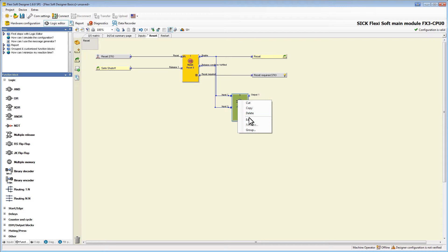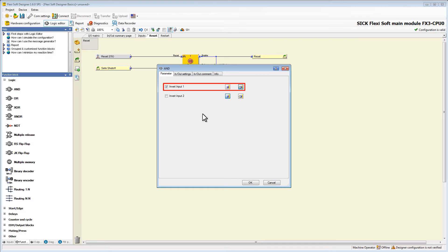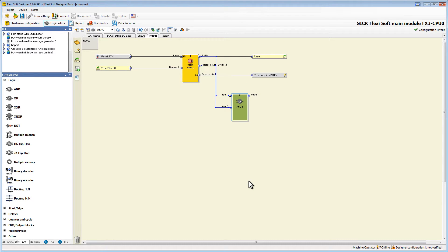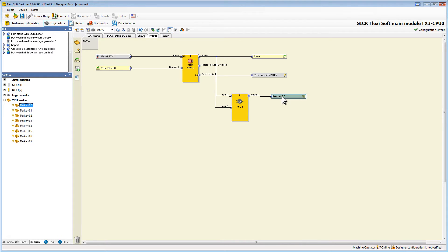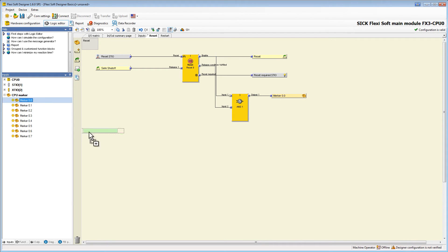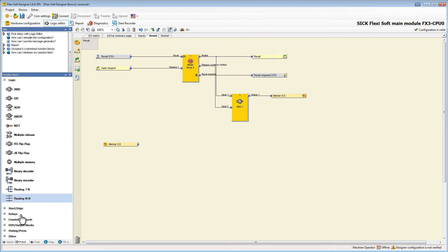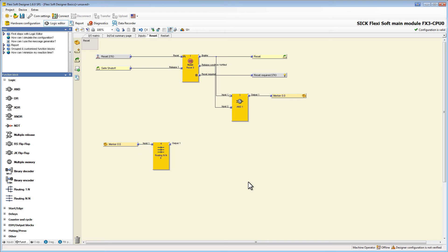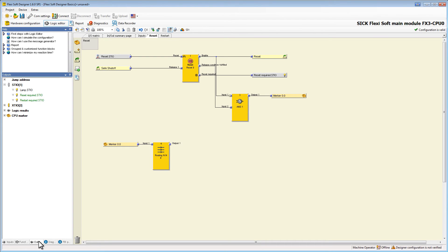However, we need to invert this input because we don't want the lamp to be on if the machine has already been reset. Therefore we right-click the block and choose edit. Here we can check the corresponding box to invert input 1. Now we can add our marker to the output of our AND block. We also need the input counterpart of our marker, which we find under inputs. It's important to use the marker with the same name as our output marker. To add a lamp to the output of the marker we need a routing block, and we change the number of inputs and outputs by opening the context menu of the function block. All that is left to do is to add the lamp.